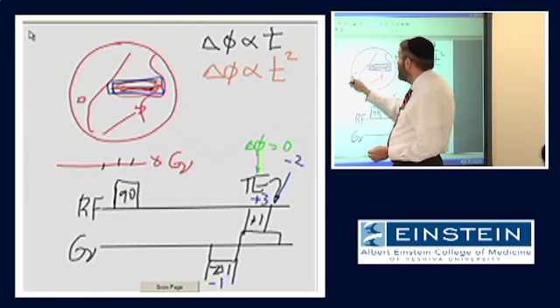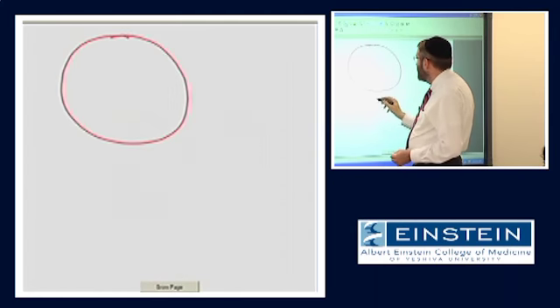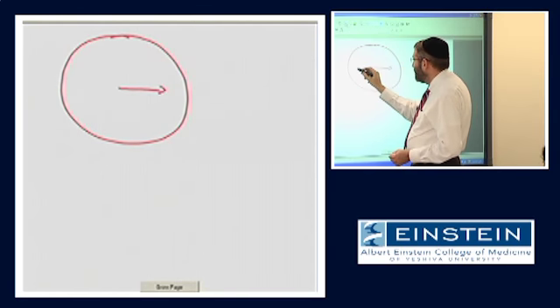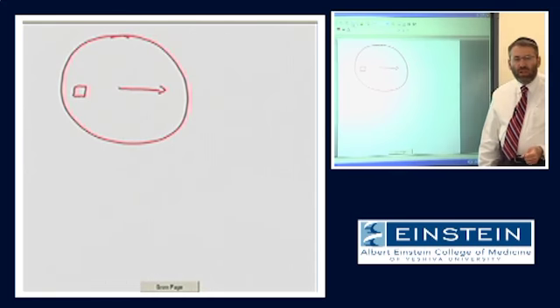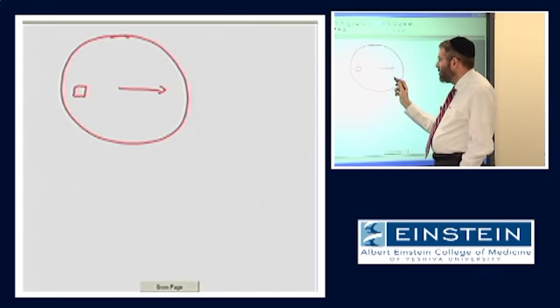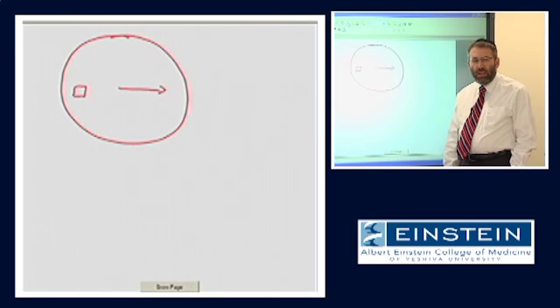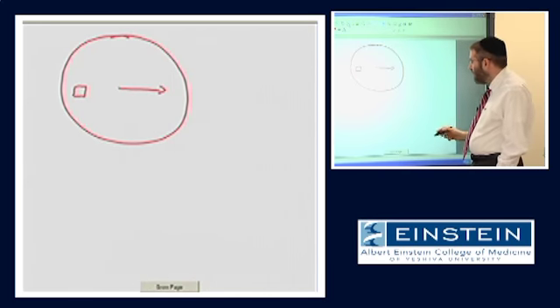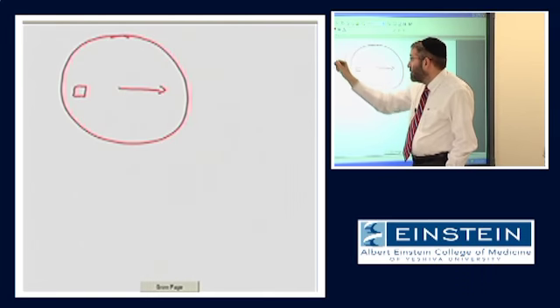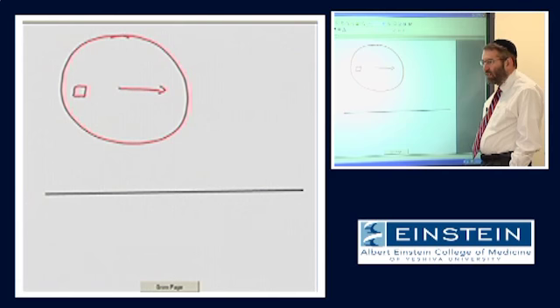It turns out that there is a way for us to generate our image where we have flow and stationary spins and avoid all that signal loss due to flow. We'll talk about examples where you would want to see signal due to flow. So is there a way to design the pulse sequence so that we can have both? Yes — and this has to do with understanding the nature of the way phase is accumulated. So let's look at how we could design our frequency encoding gradient so it would have no net effect on either stationary or flowing spins at time TE.